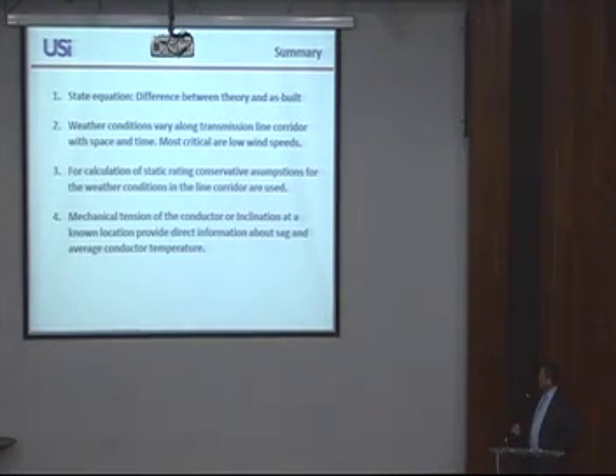As I said, the mechanical tension of a conductor, and I don't go into that, and the inclination at a given point, inclination and mechanical tension are also related one-to-one to each other. So from inclination you can calculate the tension and the other way around. So there are two parameters which provide you direct information about sag and conductor temperature, the main parameters for designing and operating the line.